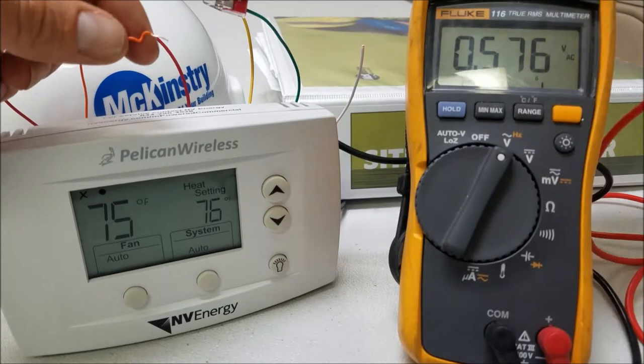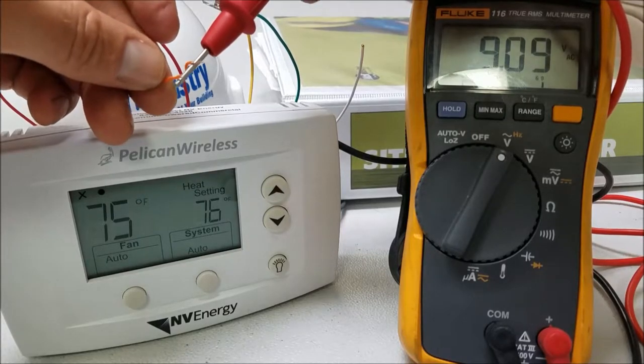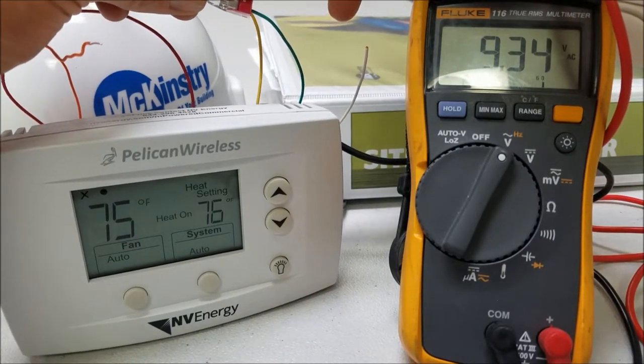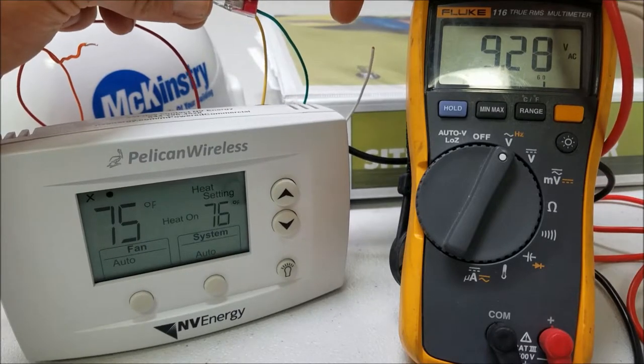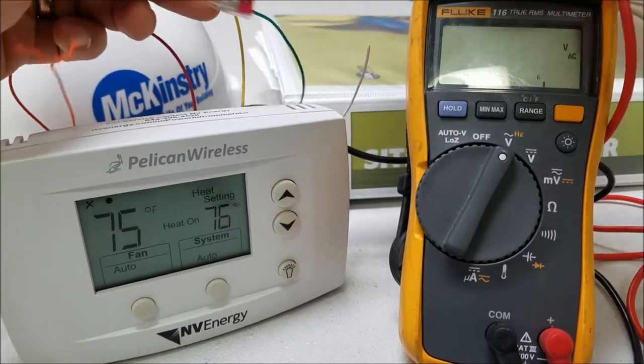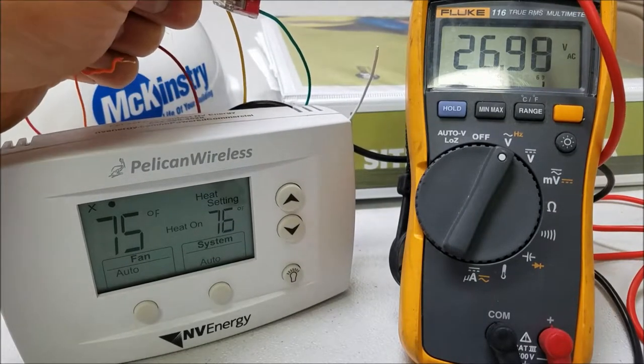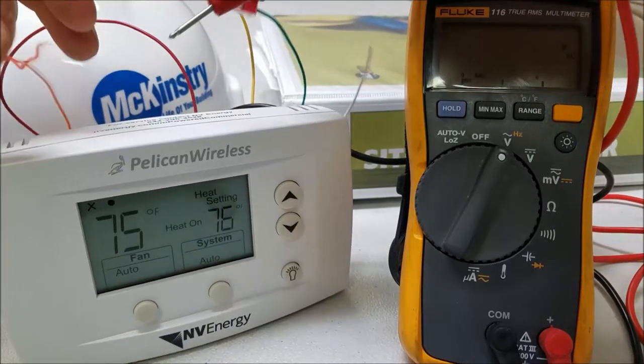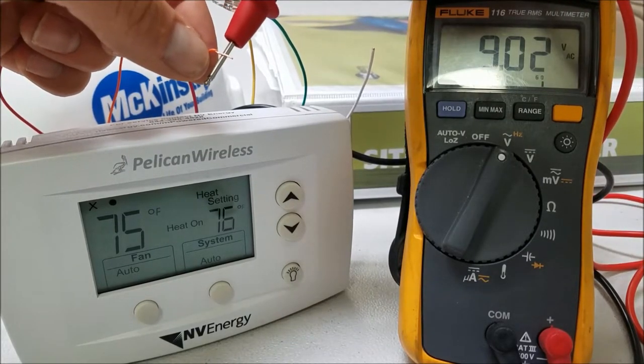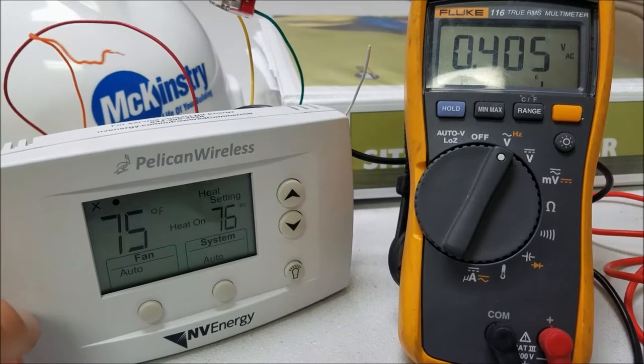Now I heard the relay click. As you can see, the orange wire connected to O is now de-energized for the reversing valve. The compressor relay just clicked — you probably saw the heat call come on — and the compressor should be coming on momentarily. The supply fan is on, and another relay click — compressor is running. Because we're in the mode where the reversing valve is energized for cooling and de-energized for heating, as you can see it's de-energized, so the unit is now in heating mode.